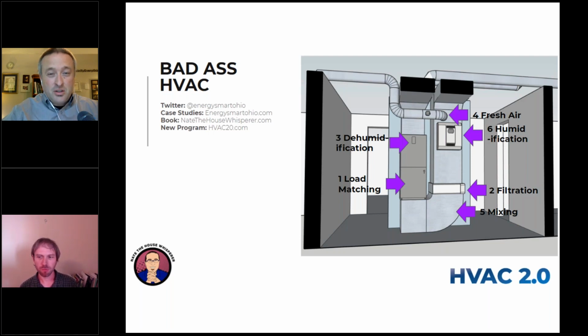If the ducts are inside the house, I'm not super worried about sealing them. It can be a nice thing to do, but you also want to check if the system has enough static pressure, because you can seal the ducts, drive the static up, and you just paid $600 to seal your ducts to kill your air handler motor two years later. Congratulations — if you'd left it alone, it wouldn't have died. So it can be nice, it depends, it would depend on the project.